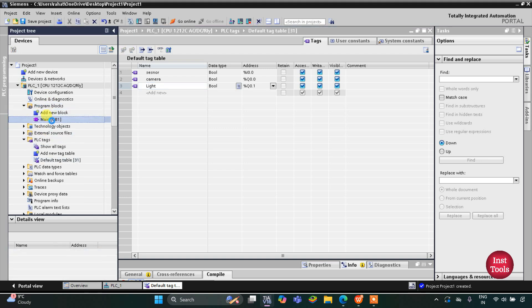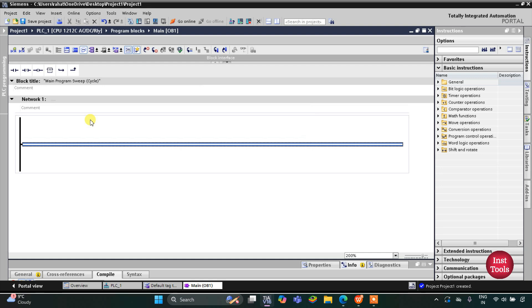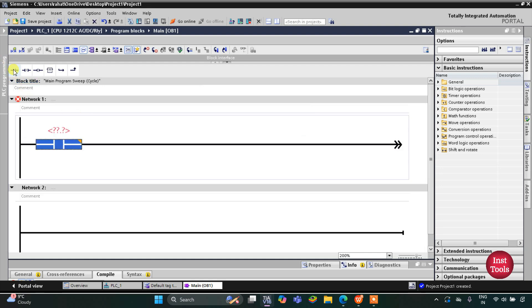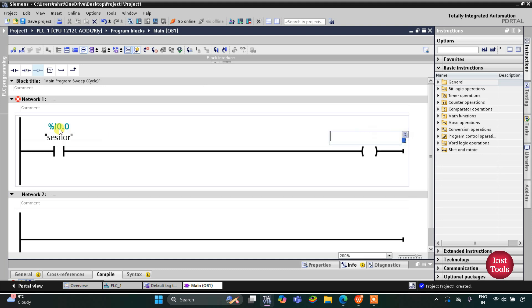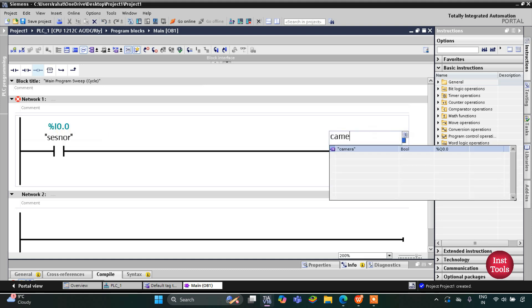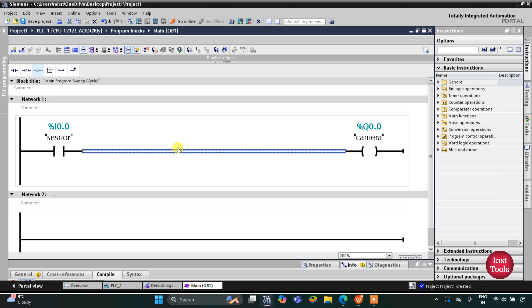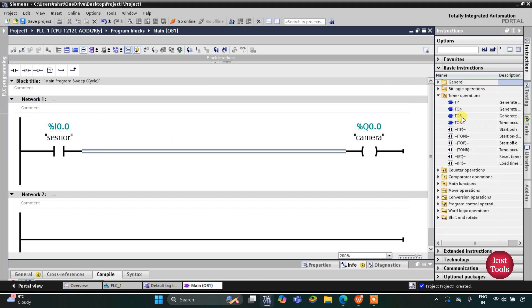We go to Program Blocks and then Main OB1 where we will draw the ladder diagram. I will zoom in and add a normally open contact and then a coil. This normally open contact will be for the sensor that detects motion, and the output is the camera. The camera should start recording for 25 seconds, so we will use a TP timer with a preset value of 25 seconds.